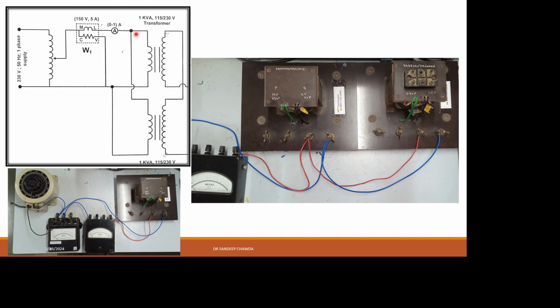The first terminal of the LV side of the first transformer is connected to the first terminal of the LV side of the second transformer, and the second terminal is connected with the second terminal. So in the second transformer, you need to identify which one is the 115 volt LV side and which one is the 230 volt HV side. The LV side terminals are connected together, terminal 1 to terminal 1, and terminal 2 to terminal 2. You just need to keep in mind which one is 1 and which is 2.